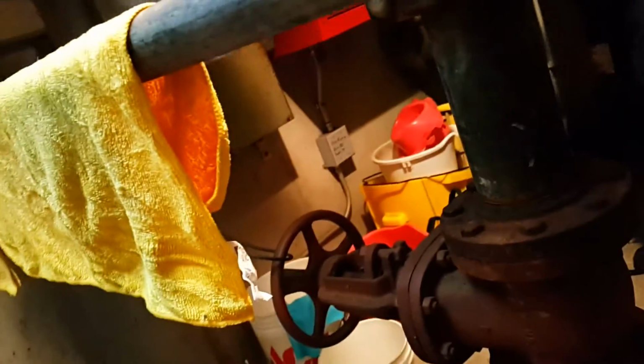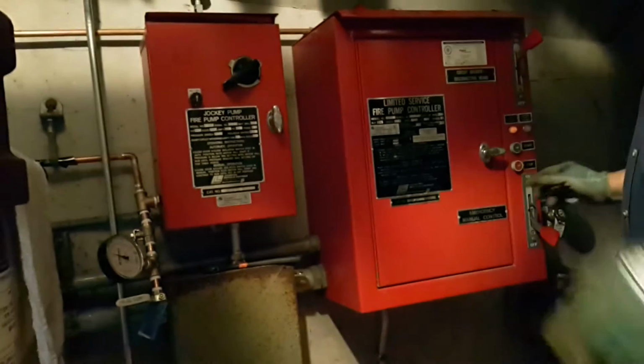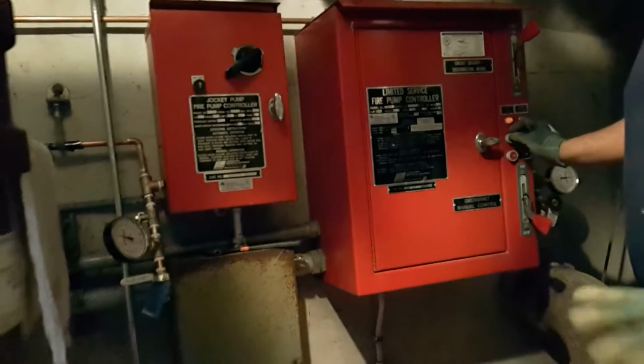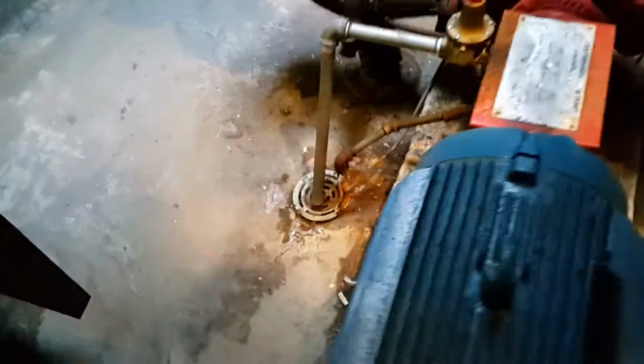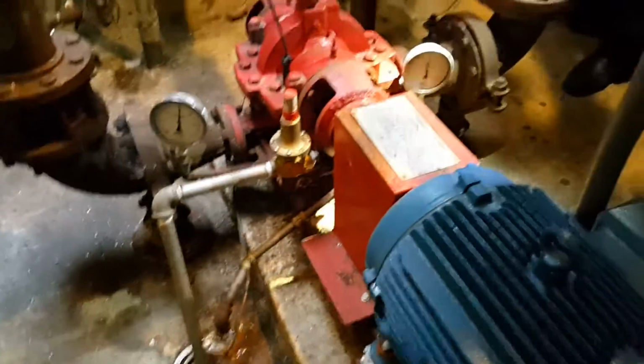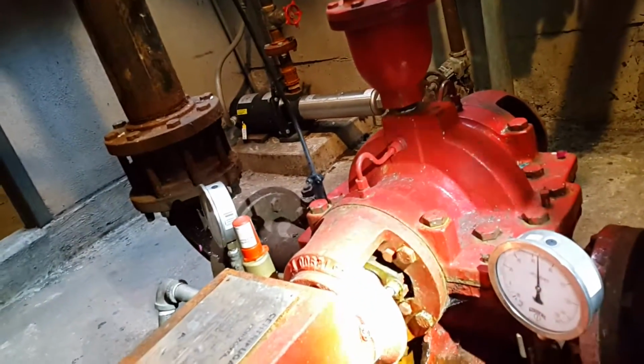So once you know that's shut, make sure your suction valve is open. All right, you do the same thing over here on this side. Start the fire pump. You do a manual start with that valve shut. All you gotta do is just make sure the fire pump starts, let it run for a couple seconds, and then turn it off. What we're looking for on the fire pump, make sure we got water on the packing pad. So I'll adjust it like maybe a little bit less on that side.